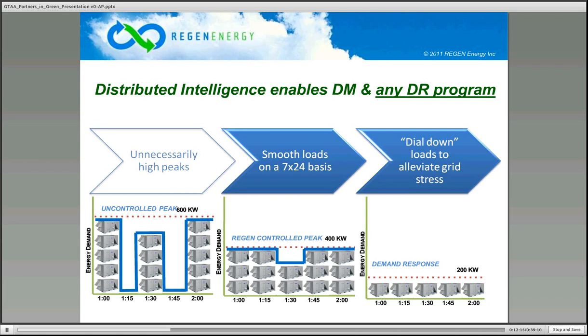Now the blue line on both graphs represents the amount of cooling you get, and you'll see that it's exactly the same amount of cooling in both cases. We're not going to save you any consumption through this particular part of the program, because all we're doing is shifting the load from one place to another. So you'll get a lower peak, but the same amount of consumption. And that's important, because it's the amount of consumption that determines how much cooling you're going to get, and that's what you want. You want the same amount of cooling, just delivered a bit more intelligently.